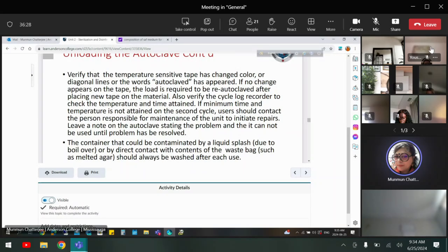So now you are going to check the temperature resistance, that is, the tape indicator, whatever you put on, whether it has changed its color or not. It will give you the basic indication that steam has been achieved. The change in the color of the tape tells you the steam has been achieved. So if no change appears on the tape, the load is required to be re-autoclaved after placing new tape on the material, because the tape you already used has been exposed to steam. So during re-autoclaving, you have to put on a new tape.